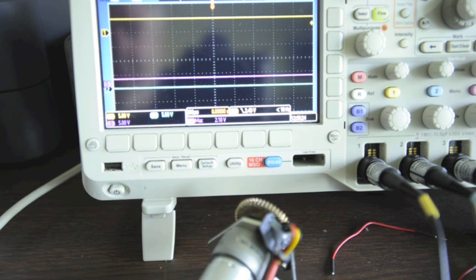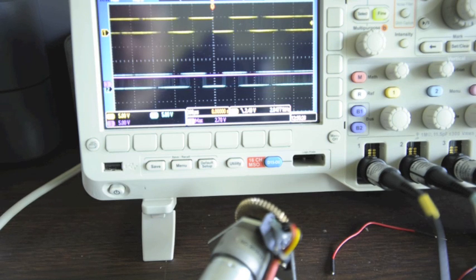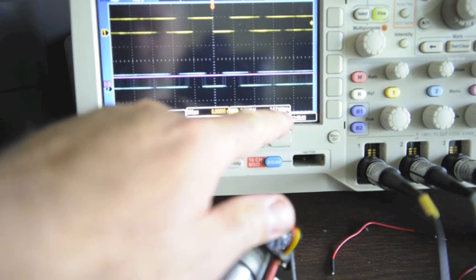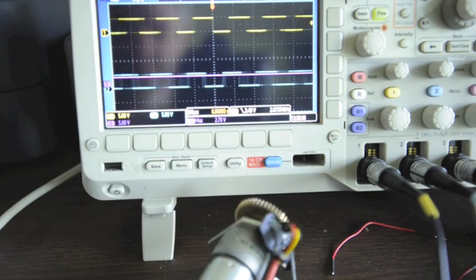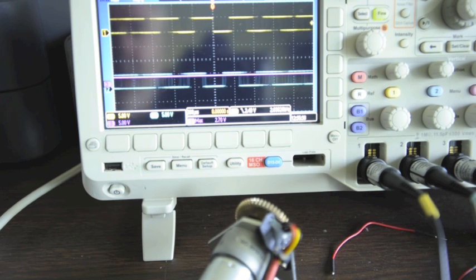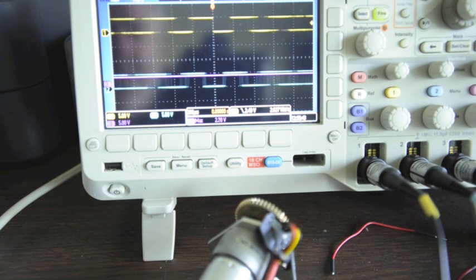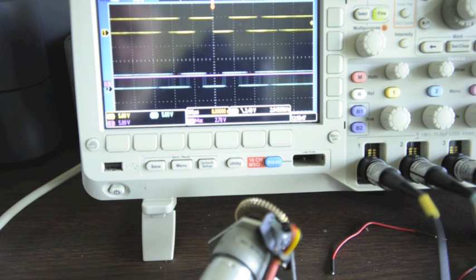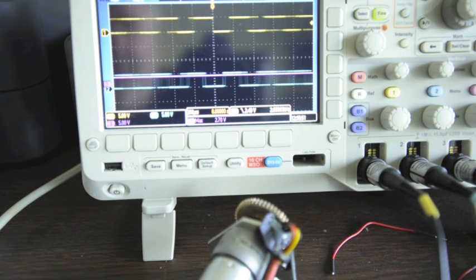Now let's turn this back up a little. Now there's the minimum speed that we're going to get it going. Notice that the encoder frequency is about 2.6 kilohertz. I'll explain that in the text. Actually, the encoder has 256 ticks per revolution of the actual motor.